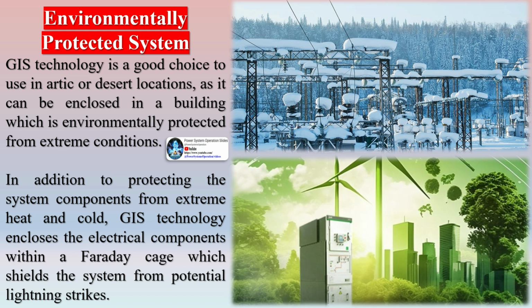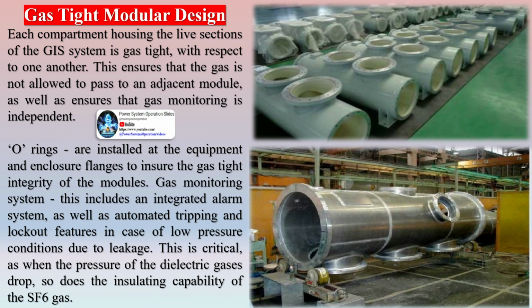GIS technology is a good choice to use in Arctic or desert locations, as it can be enclosed in a building which is environmentally protected from extreme conditions. In addition to protecting the system components from extreme heat and cold, GIS technology encloses the electrical components within a Faraday cage, which shields the system from potential lightning strikes.